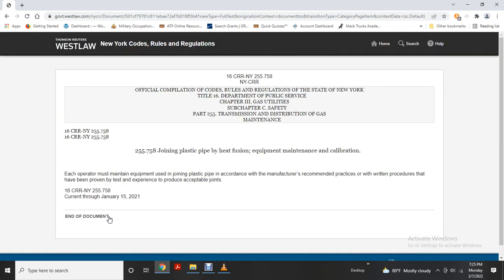Alright, joining plastic pipe with heat fusion equipment and maintenance for calibration. Each operator must maintain equipment used to join plastic pipe in accordance with manufacturer recommended practice, with written procedures that have been proven by test or experience to produce acceptable joints.